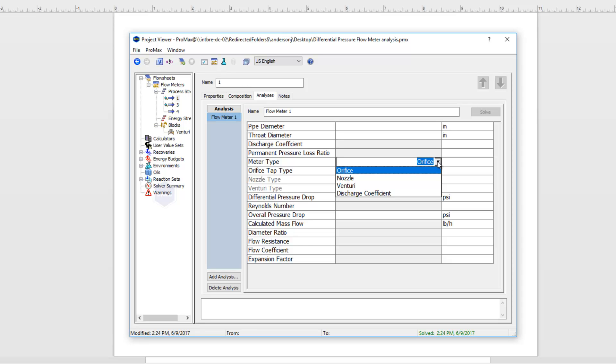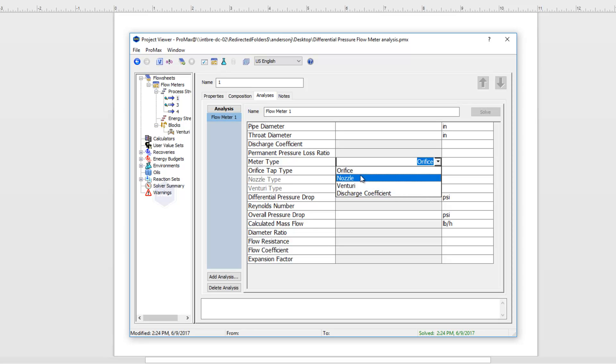For each of these types, if we've chosen that type, PROMAX will calculate the discharge coefficient and things associated with that meter. If we have a meter that doesn't fall in any three of those categories but we do know the discharge coefficient, we can use this discharge coefficient option and just manually put in our discharge coefficient.